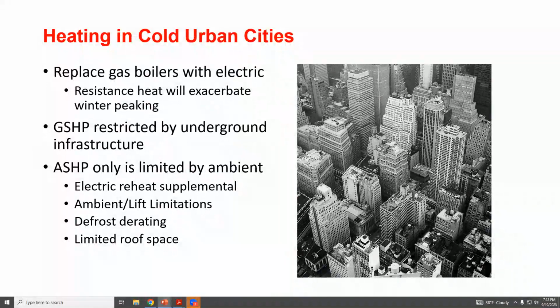But then if we also take a look at electric heat - if we go from just gas to electric, it could drive up peak demands. If we start looking at heat pumps, it works a little bit better because we're working off the concept of heat of compression, and we start looking at COPs being a lot higher than 1, which would be just electric resistance. Heat pumps a lot of times might be in the 2s, 3s, 4s, depending on ambient and depending on some of your conditions if you're looking at water source.